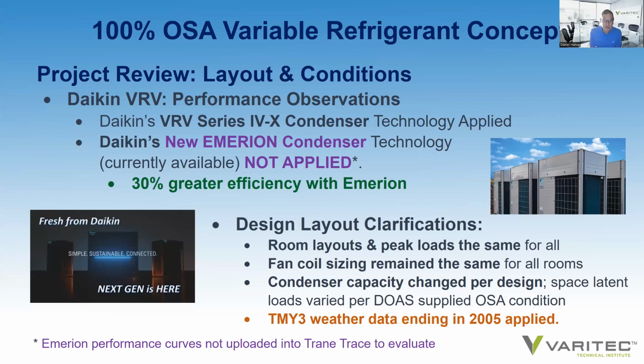So let's have some design clarifications as we move forward with our analysis. Room layouts of all indoor units and peak loads remain the same for all 3 design scenarios. Fan coil sizing remains the same for all rooms. Condenser capacities changed per design because the latent load changed depending on which design we used. Also be aware that the evaluation was done using TMY3 weather data, which ended in 2005. Studies have demonstrated that our current weather data has seen a considerable increase in temperature since 2005. So the values that we're going to see are very conservative values for energy savings.